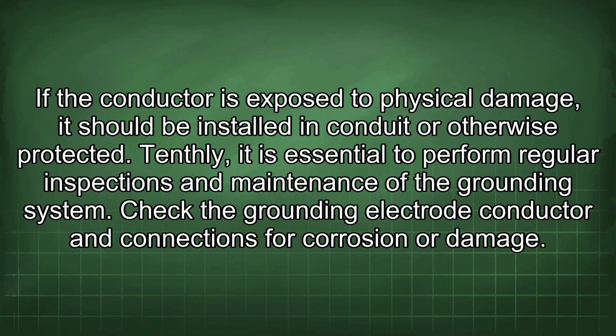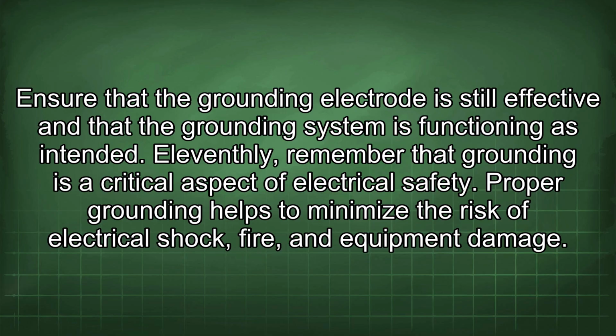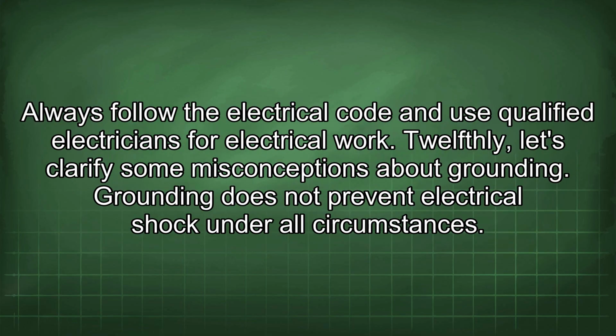Tenthly, it is essential to perform regular inspections and maintenance of the grounding system. Check the grounding electrode conductor and connections for corrosion or damage. Ensure that the grounding electrode is still effective and that the grounding system is functioning as intended. Eleventhly, remember that grounding is a critical aspect of electrical safety. Proper grounding helps to minimize the risk of electrical shock, fire, and equipment damage. Always follow the electrical code and use qualified electricians for electrical work.